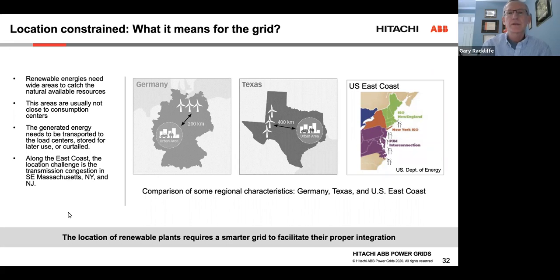In Texas, wind generation has been developed. This is onshore wind, developed in the west. We have about 400 kilometers or 240 miles to bring that power to the load centers, which would include Dallas and Austin, San Antonio, and Houston. Those are all towards the eastern part of the state. There we have overhead lines, but we've also implemented solutions such as series capacitors to reduce the impedance and losses of the overhead lines, as well as STATCOMs to provide voltage support and relax the transient stability limits of the transmission lines under heavy loading.